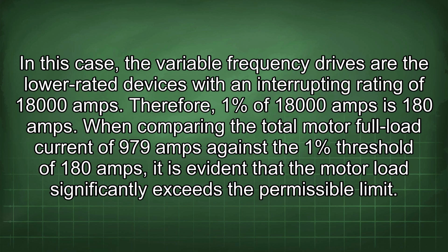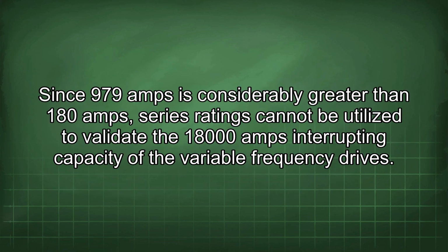When comparing the total motor full load current of 979 amps against the 1% threshold of 180 amps, it is evident that the motor load significantly exceeds the permissible limit. Since 979 amps is considerably greater than 180 amps, series ratings cannot be utilized to validate the 18,000 amps interrupting capacity of the variable frequency drives.